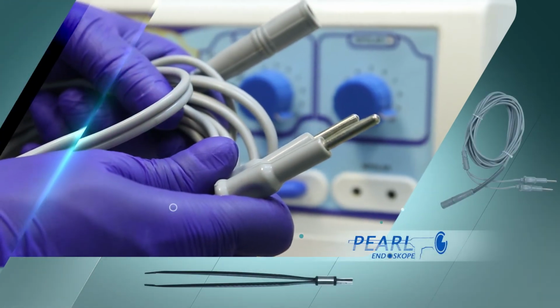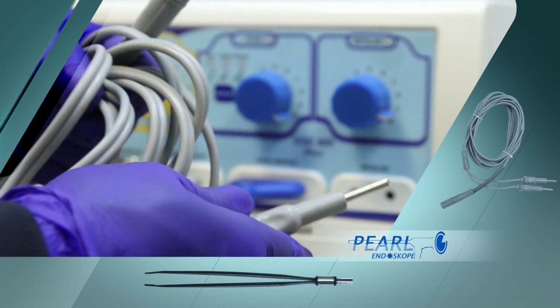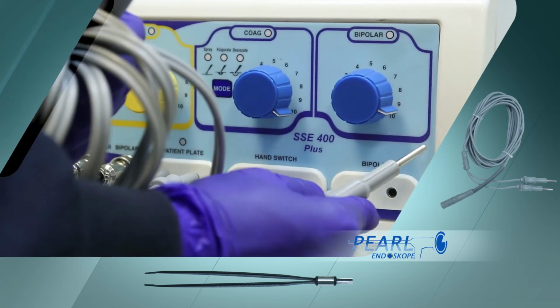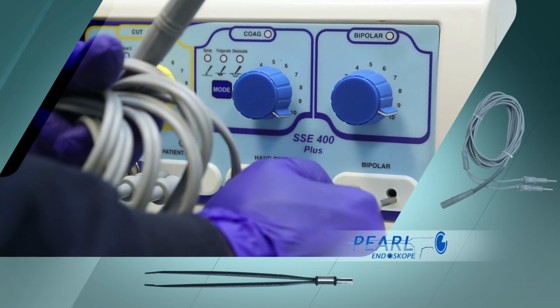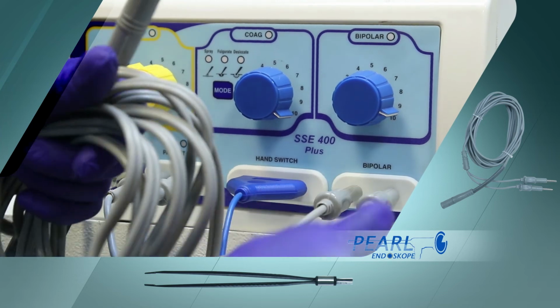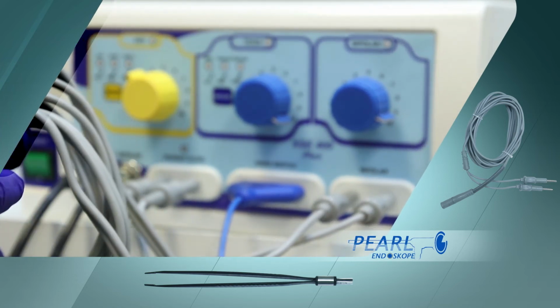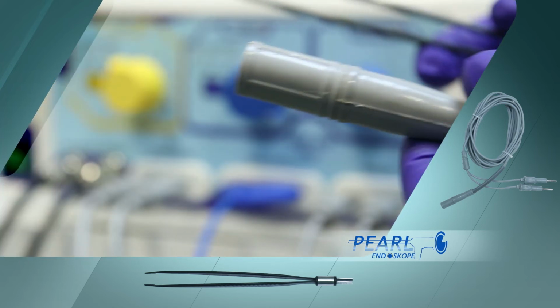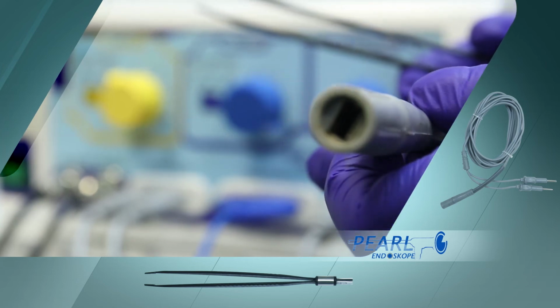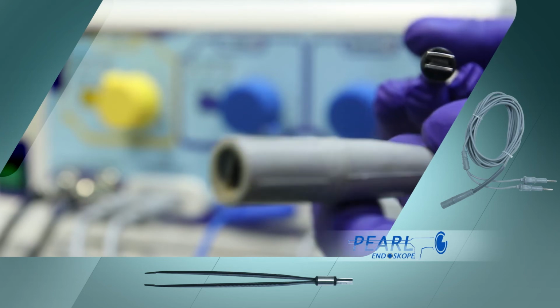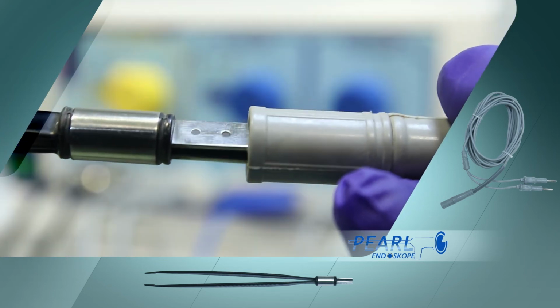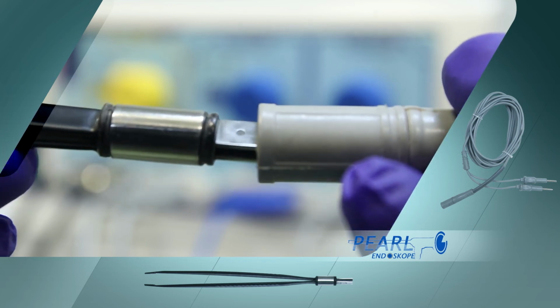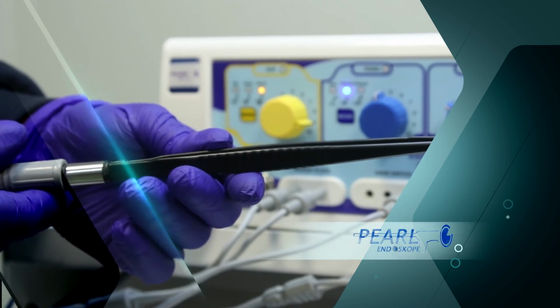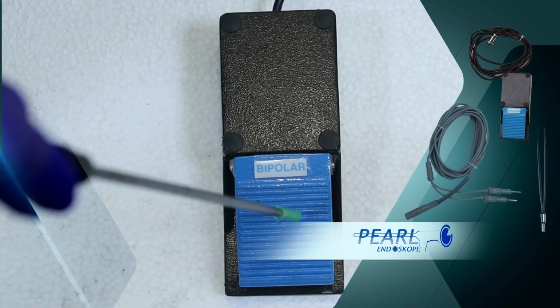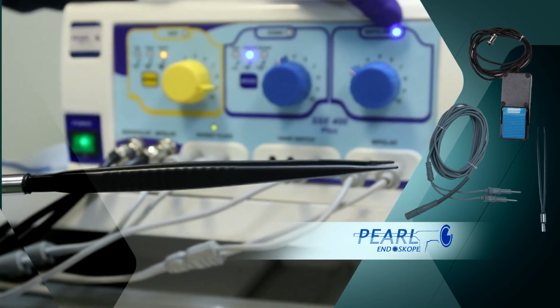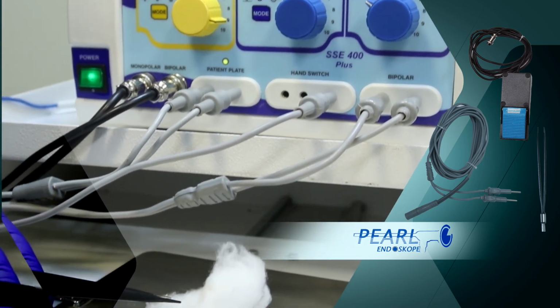This is the bipolar cable. This point is connected to the bipolar port. This portion will be connected to the bipolar forcep. We can attach the forcep as shown. The bipolar forcep is now ready for use with the help of the bipolar foot switch. The LED lights up when the bipolar forcep is in use.